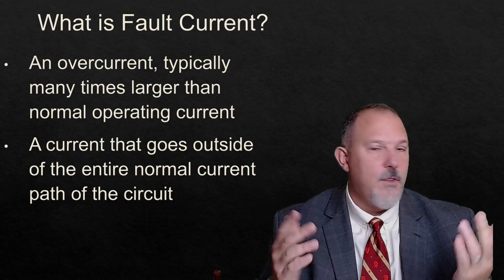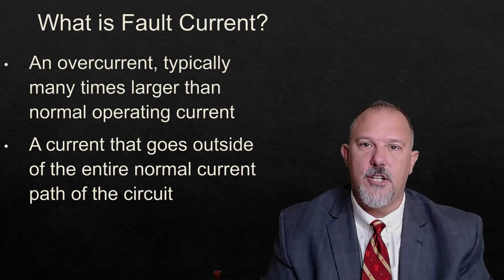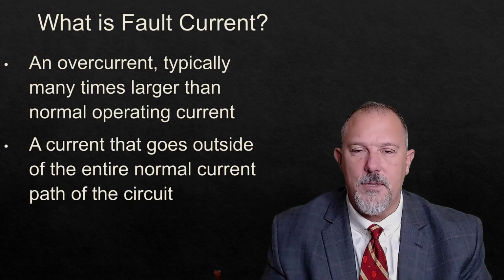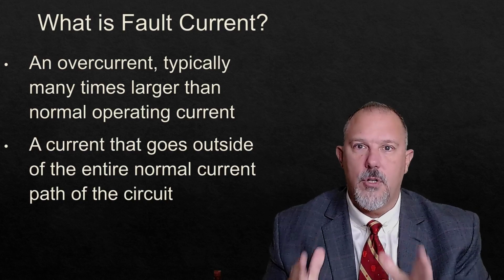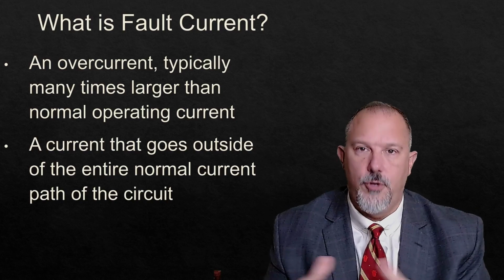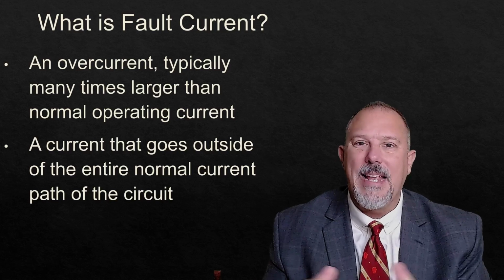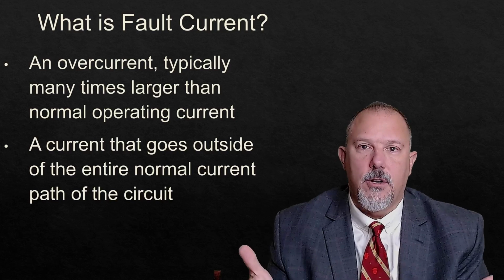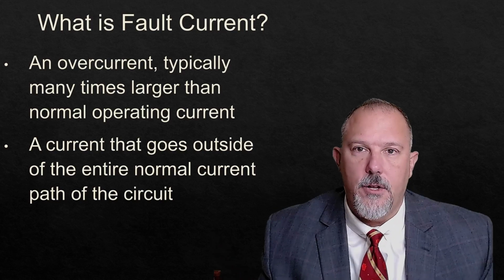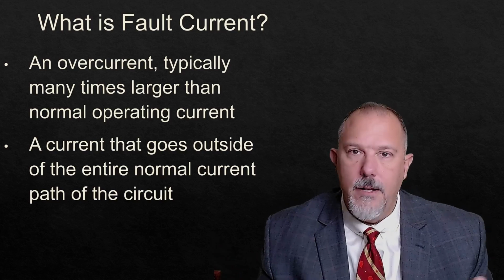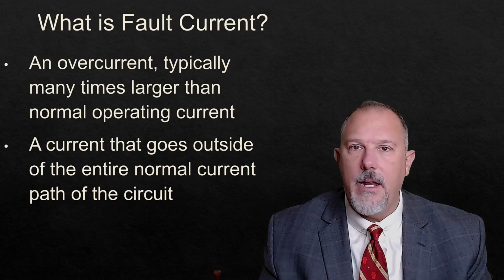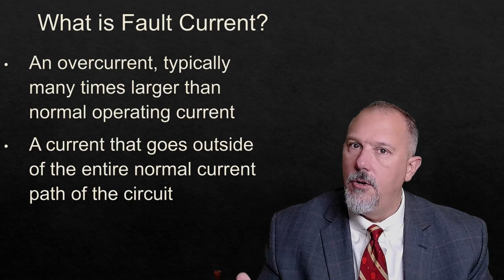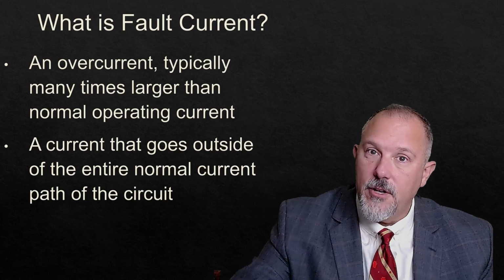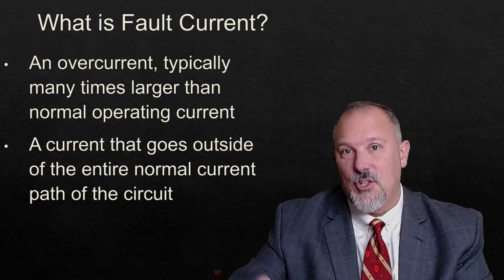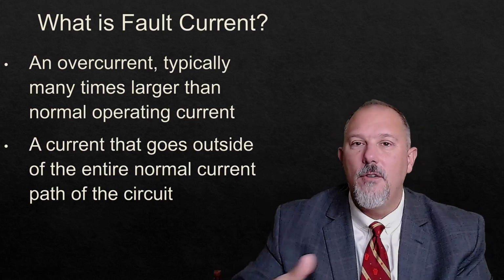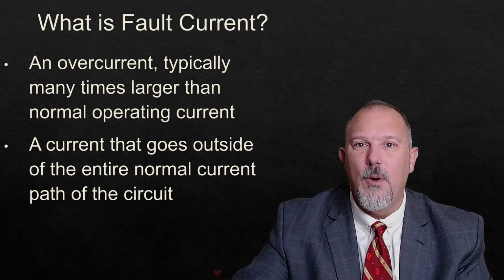But if you're sitting in the house or in your industrial facility, and all of a sudden a circuit breaker trips, and you say, okay, what was going on? I don't have any load being added. Say it's a lighting circuit. All your lights are on. They're always on. You never have an overload because you can't add anything else. You know it wasn't an overload. Now you have to find the short circuit. Clear that fault. And when you find that short circuit, you'll know if it was a ground fault, if it was a bolted fault. You'll figure out what that was.